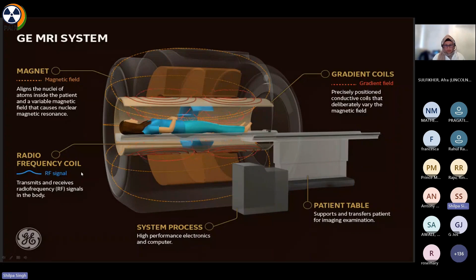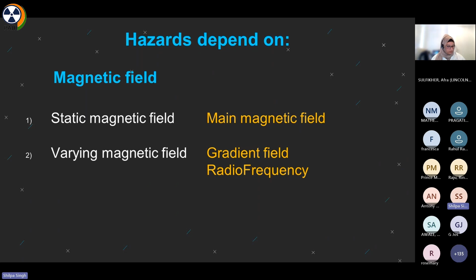So basically, these hazards depend on the classification of the magnetic field. There is one which is called the static magnetic field, which does not change with time or with direction. The other one is called the varying magnetic field. This varying magnetic field does change with direction and/or time. The static magnetic field is the main magnetic field which we insert the patient in. The varying magnetic field is, number one, the gradient field, which changes from time to time as we use different pulse sequences. And radio frequency, when we want to apply the RF pulses and collect the signal. These two are both varying magnetic fields.